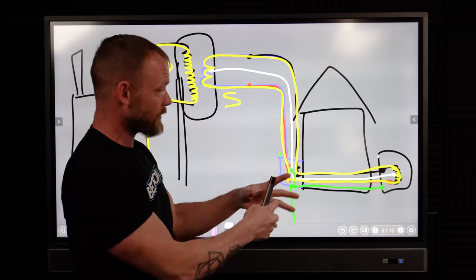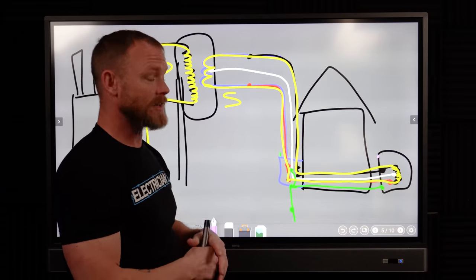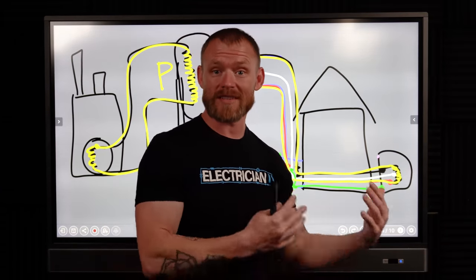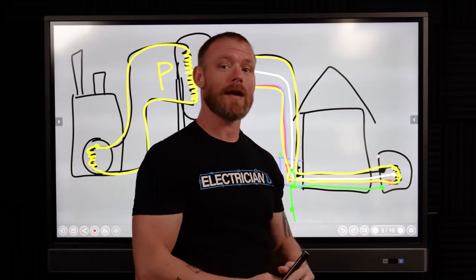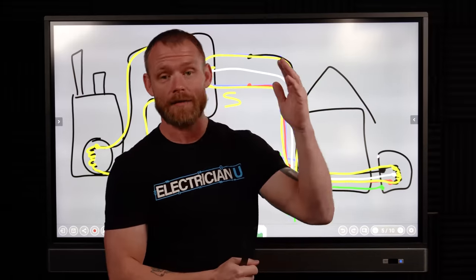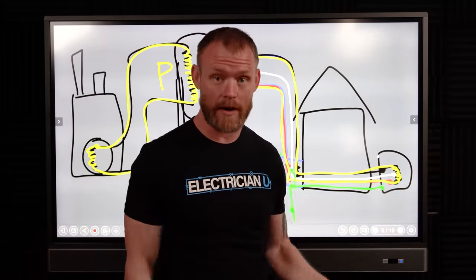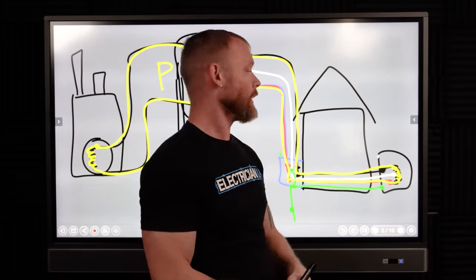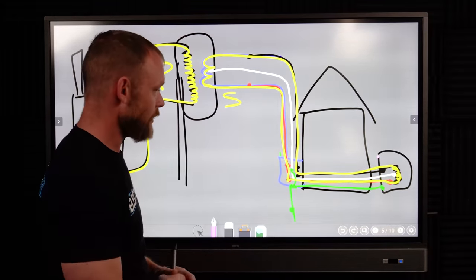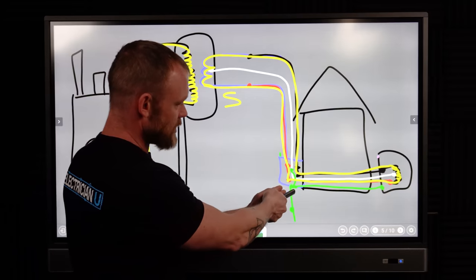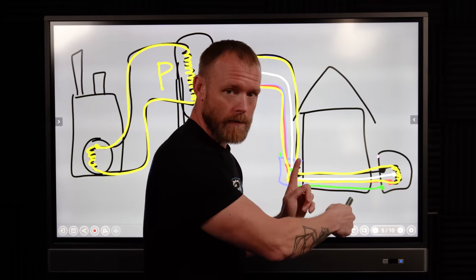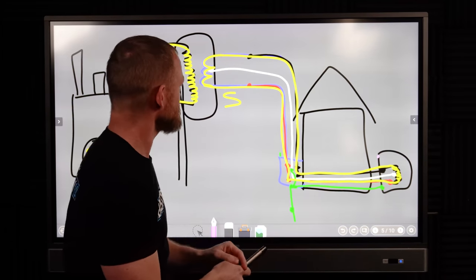The amount of current that flows is why we determine different electrical service sizes — we might have a 400 amp service, a 100 amp service, or a 1200 amp service. You'll notice there's a green conductor only on the secondary side — an equipment grounding conductor does not come from the utility company's transformer.